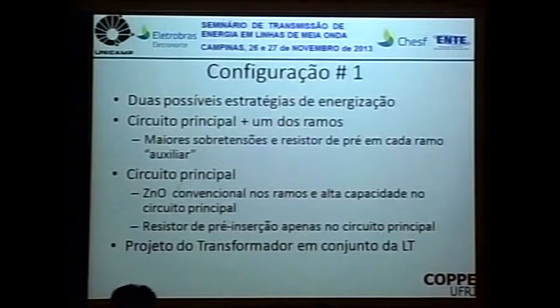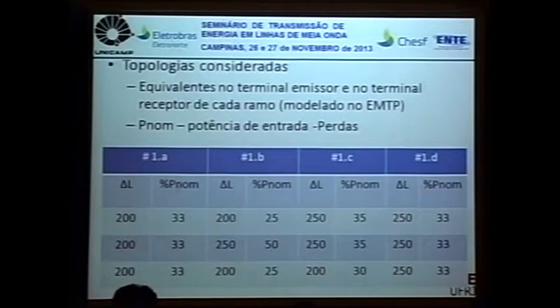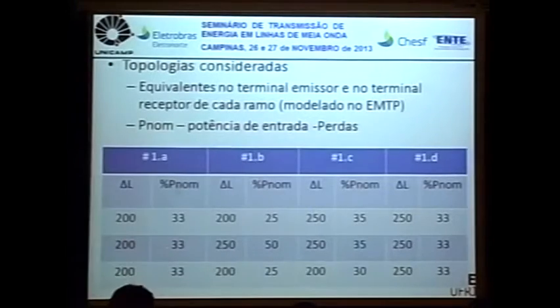the line for the demands that the line has, because as we have in the system, some transformers need to be energized together with the line because the line causes a resonance, so it cannot be energized. So you need to be careful with the transformer. The transformer project needs to be in a way that is not affected by the behavior of the line.